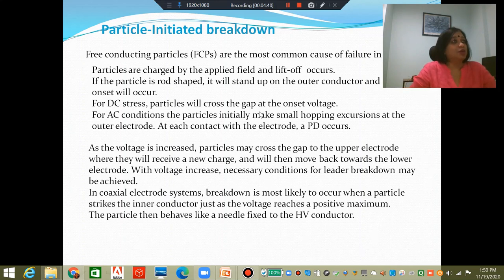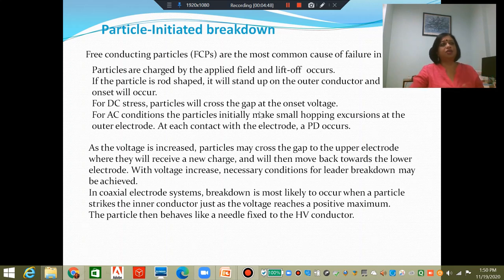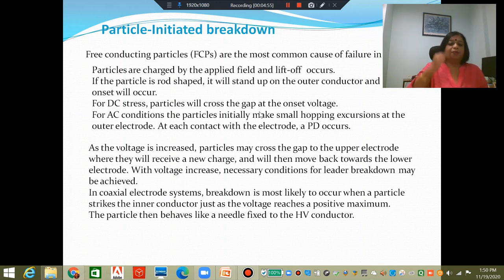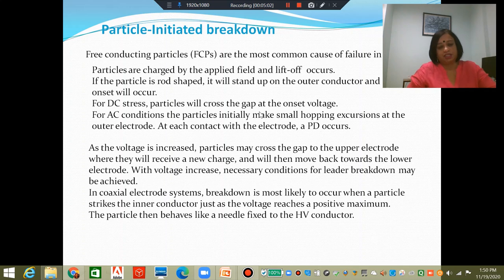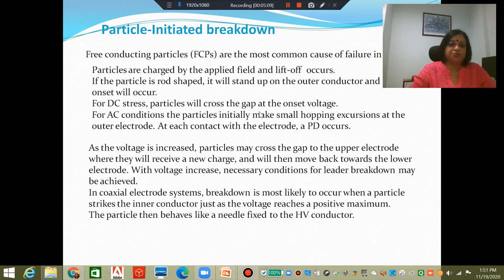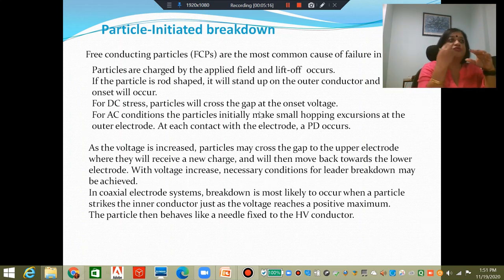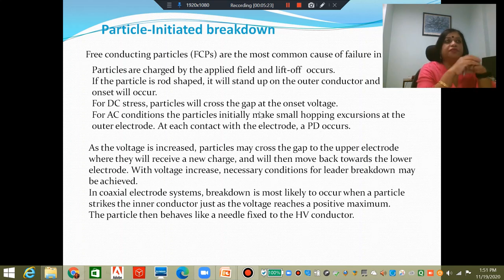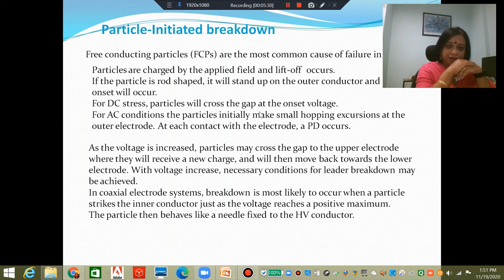In these cases, there would be considerably high partial discharges, and these partial discharges may transform into complete discharges. Complete breakdown is most likely to occur when a particle strikes the inner conductor — either because of DC traversal, or because of AC hopping when the inner conductor is at positive maximum. Particle-initiated breakdown due to free conducting particles is the most common cause of failure. Apart from particles traversing, there might also be particles on conductors due to sharp protrusions, embedded structures, or particles embedded in the epoxy insulation, which can cause breakdown at high voltages.